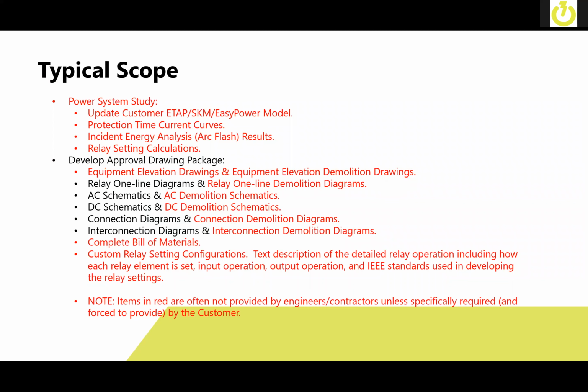We also develop an approval drawing package. That approval drawing package has full equipment elevation drawings and equipment elevation demolition drawings. Make sure that equipment that we're taking out matches the equipment that you want to get put in. Relay one-line diagrams and relay one-line demolition diagrams, AC schematics, AC demolition schematics, DC schematics, DC demolition schematics, connection diagrams showing point-to-point wiring, and connection demolition drawings, again, point-to-point wiring that's being taken out, along with any interconnection diagrams and interconnection diagram demolition drawings. We also do a complete bill of materials showing you all the equipment that's being added, full part numbers and manufacturing.